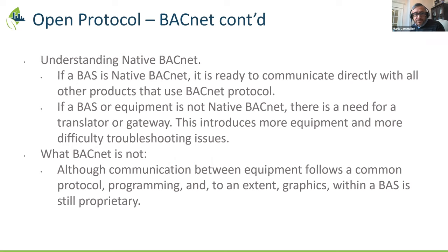What I want to highlight too is what BACnet is not. There's a perception that although communication between equipment follows a common protocol, things like programming and to a certain extent graphics within a BAS are still very much proprietary. So if you have a Siemens, Delta, or a Reliable Controls system, they can communicate with each other in terms of reading, but the inherent programming done within the actual panels and controllers themselves is still very much proprietary. Nothing wrong with that, but I wanted to make sure we understand that even though there's a common protocol to communicate, certain things remain proprietary.